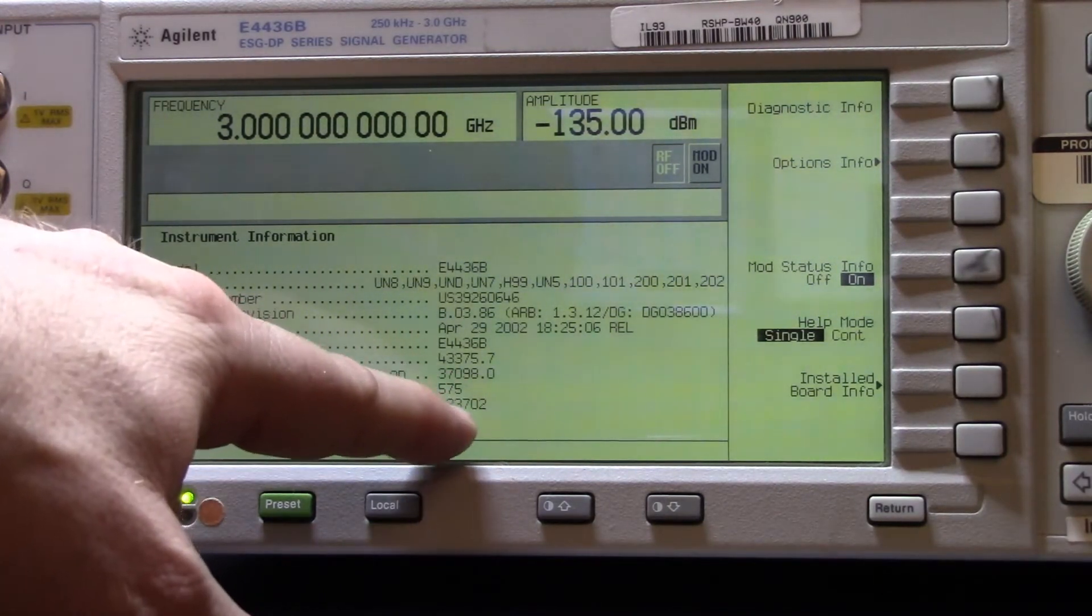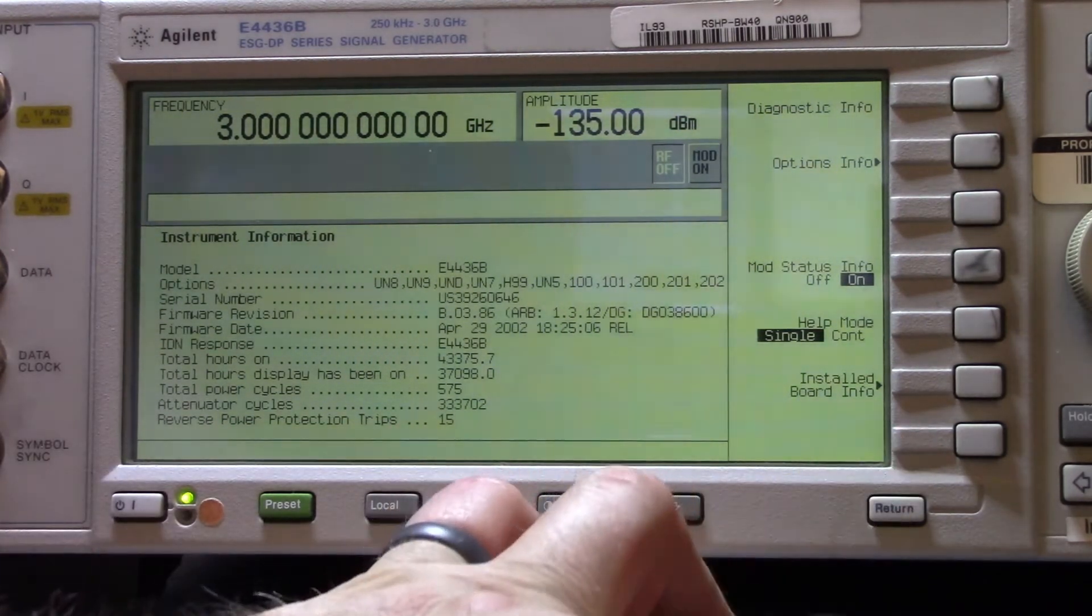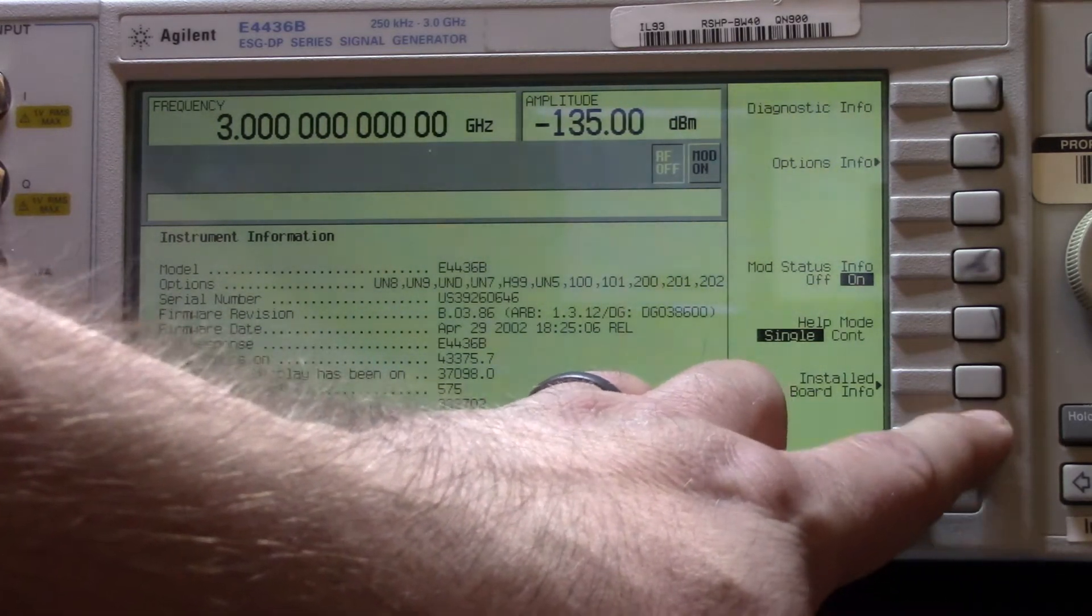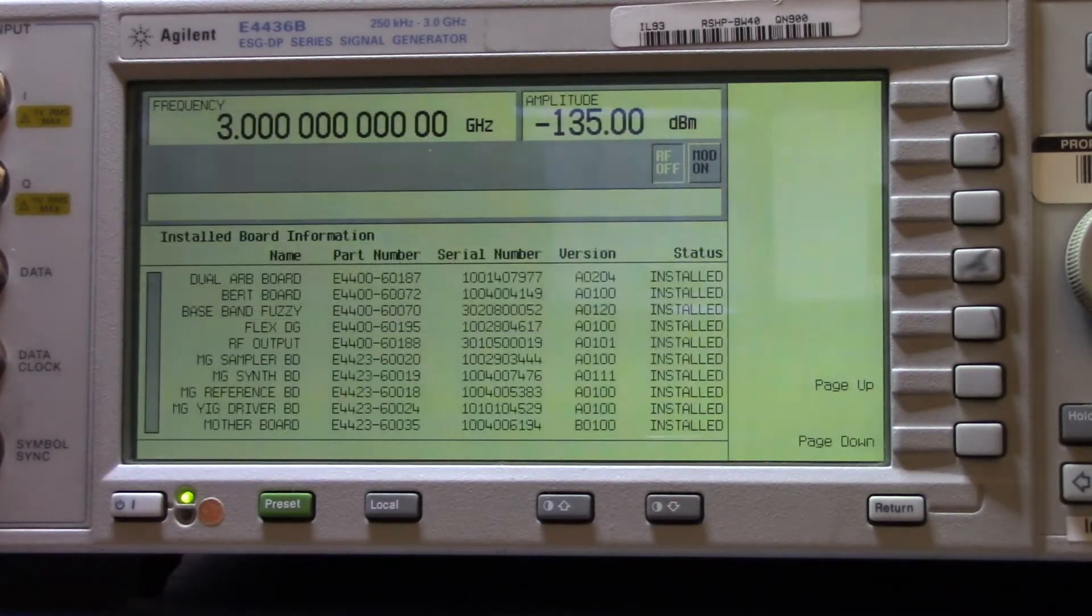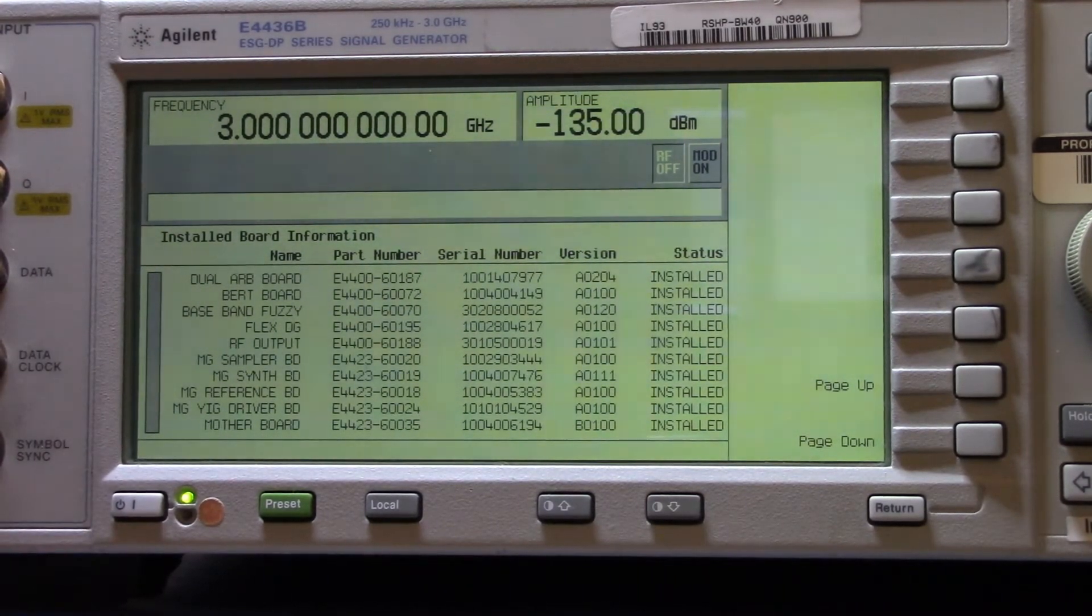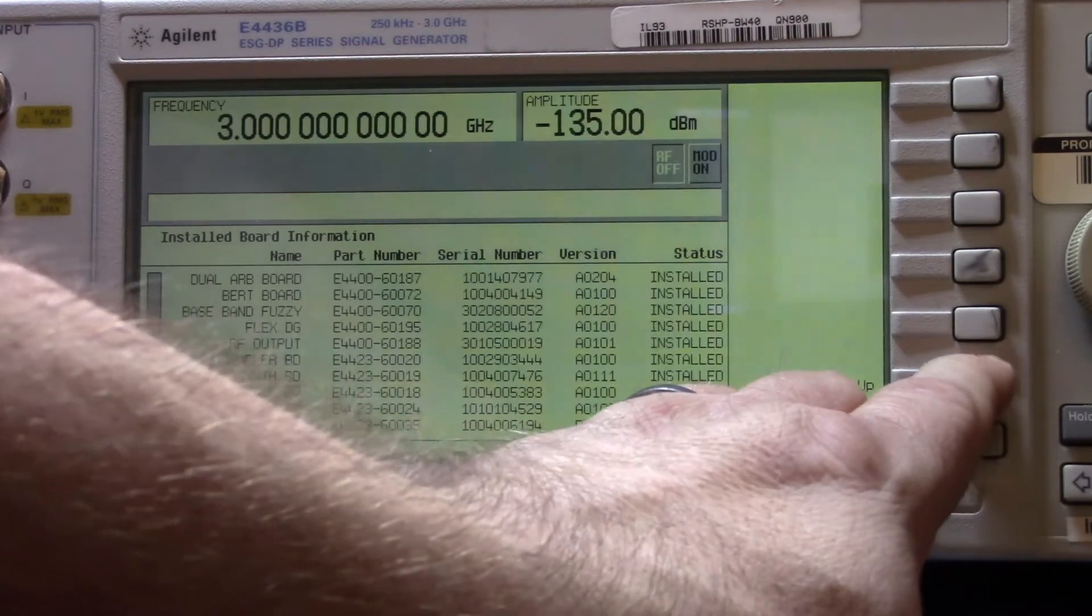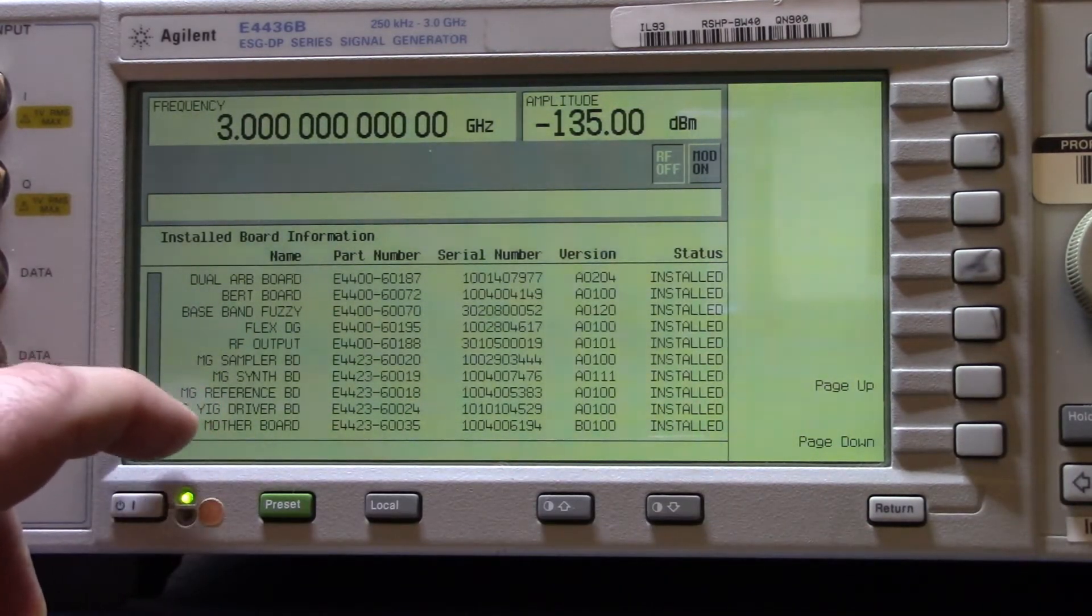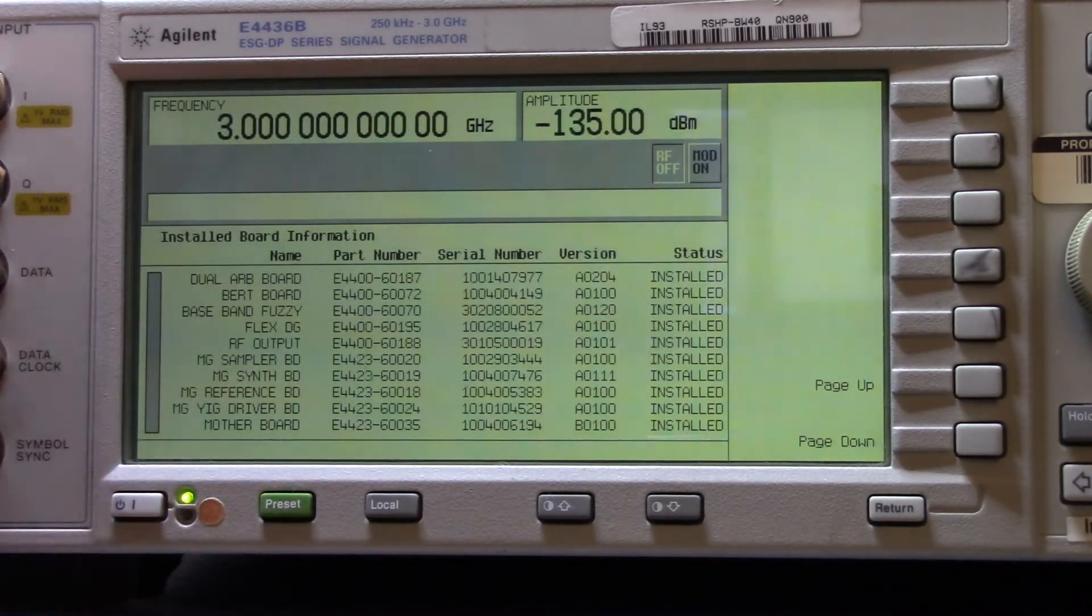Let's see instrument info, diagnostic info. Attenuator cycles 333,000. The attenuator is probably not going to be in calibration very much longer. They usually tell you that stuff so you know when the attenuators need to be replaced.